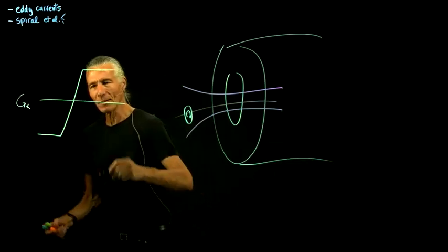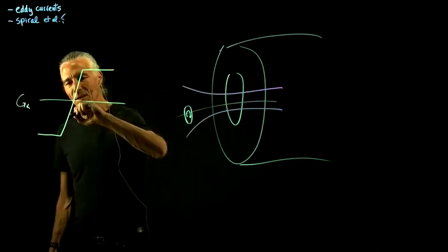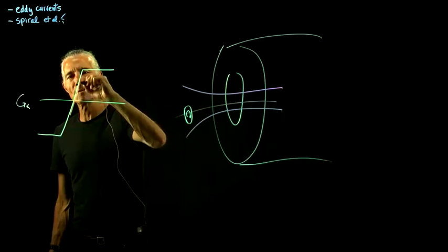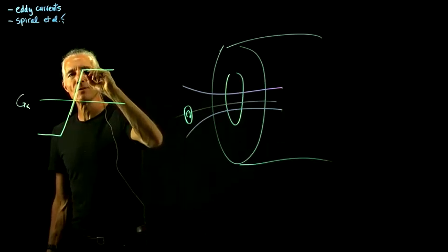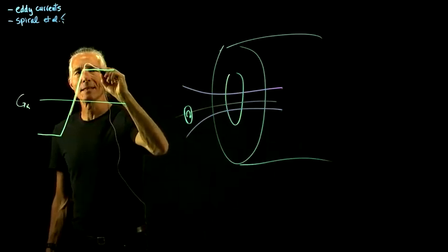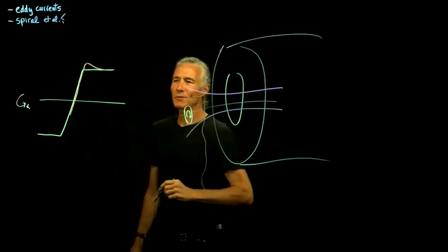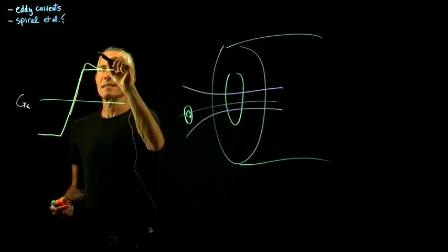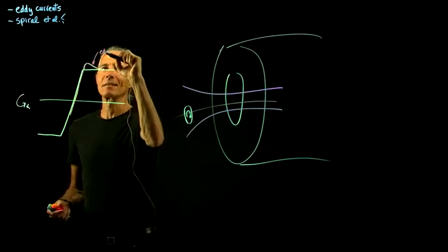When you're on the straight, it's not too bad. The measured magnetic field will be about right. But when you suddenly go to a constant current through the gradient coils, you'll get something that looks like that. There's an overshoot. And what's causing that? The eddy currents.